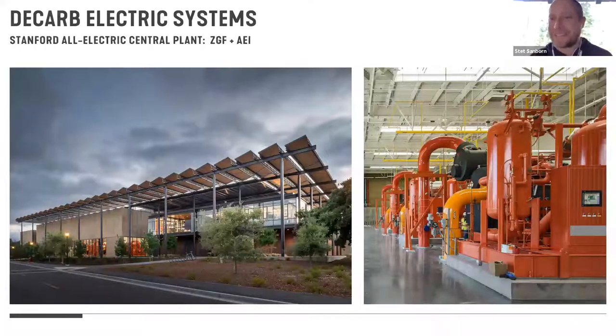Now, clearly, they have a few dollars to spend. It's probably the most gorgeous central plant I've ever seen in my life. I would eat off the floors in the central plant. It was really nice. But this project uses heat recovery chillers, or heat recovery heat pump chillers, and a massive amount of thermal energy storage. So behind this facade, what you don't see are the several million gallons sitting just behind here of thermal energy storage, both on the hot water side and the chilled water side. So they're able to manage their loads on their campus and do thermal energy storage, maintain the all-electric design. And it's just a phenomenal system.